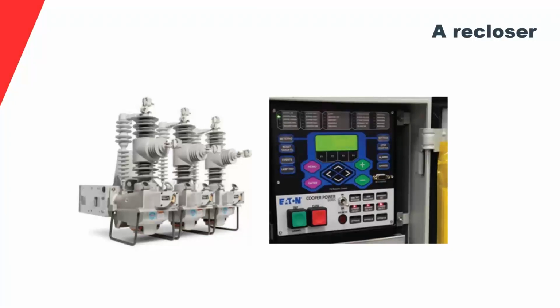no, if I have to test a recloser, it's only the high voltage part that I have to test. And that is just not true. In my opinion, it's better to define the recloser as the whole thing. And then, yeah, it has two parts, and both parts need to be tested to some extent, right?